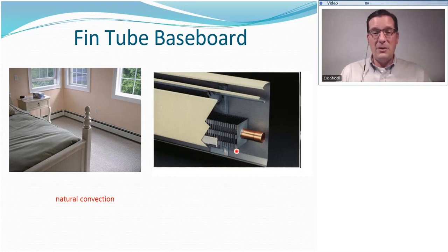Look to see if the condition of the shroud is good. Make sure that it's there. If the whole shroud is just missing and there's just this heating element sitting there, it's not going to be nearly as effective. This whole thing is designed and sized to promote that circulation of air. And if the shroud is missing and there's just the fin tube element there, it's not going to be nearly as effective. So a couple of things to keep in mind about fin tube baseboards. They are absolutely everywhere, because they were so easy to install.